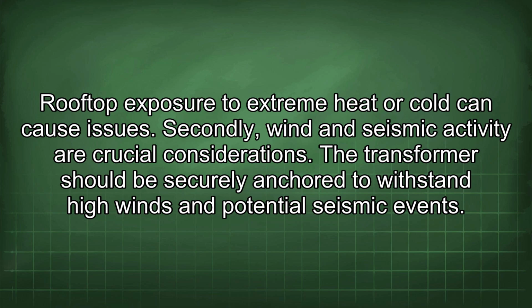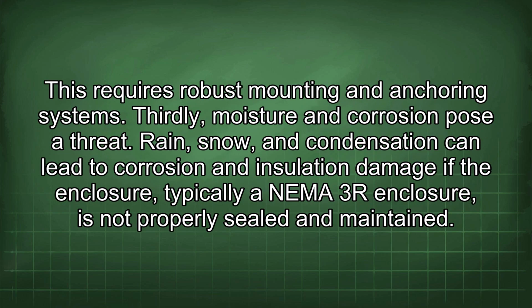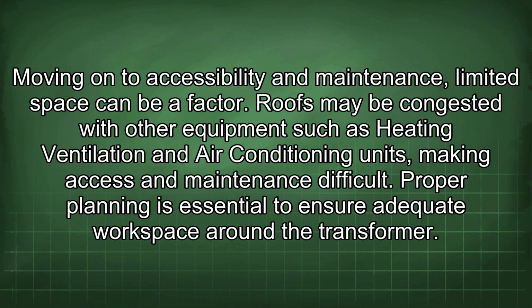Secondly, wind and seismic activity are crucial considerations. The transformer should be securely anchored to withstand high winds and potential seismic events. This requires robust mounting and anchoring systems. Thirdly, moisture and corrosion pose a threat. Rain, snow, and condensation can lead to corrosion and insulation damage if the enclosure, typically a NEMA 3R enclosure, is not properly sealed and maintained. Moving on to accessibility and maintenance, limited space can be a factor.